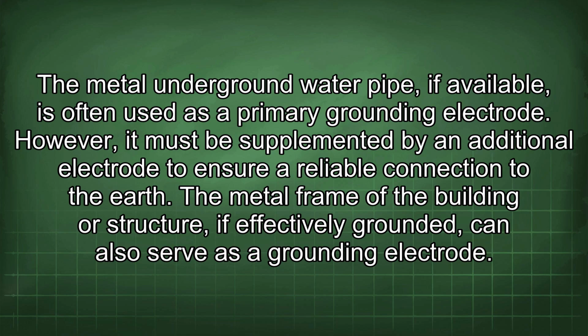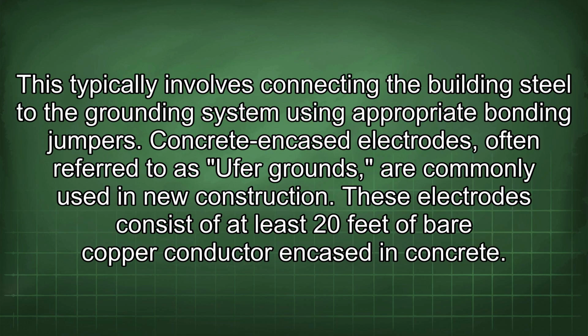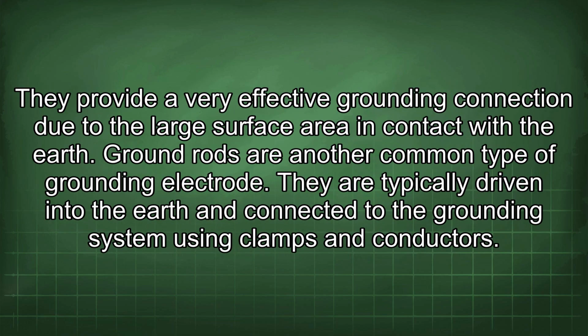The metal frame of the building or structure, if effectively grounded, can also serve as a grounding electrode. This typically involves connecting the building steel to the grounding system using appropriate bonding jumpers. Concrete encased electrodes, often referred to as Ufer grounds, are commonly used in new construction. These electrodes consist of at least 20 feet of bare copper conductor encased in concrete. They provide a very effective grounding connection due to the large surface area in contact with the earth.